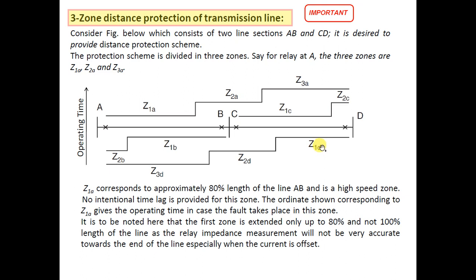Z1A corresponds to 80% of the length of line A-B — it will cover up to 80% of the line length, and it is the high-speed zone with the least operating time. The first zone as discussed does not provide protection for the full 100% length of the line; generally it covers up to 80%.